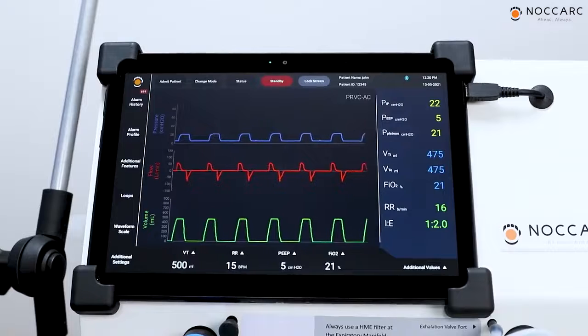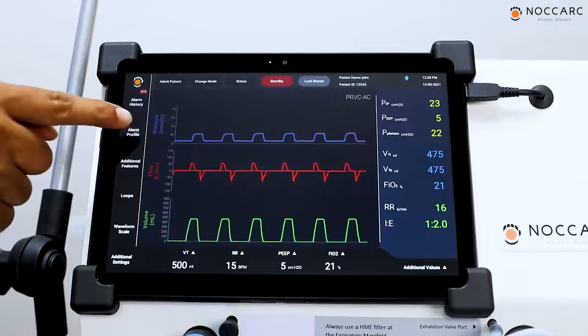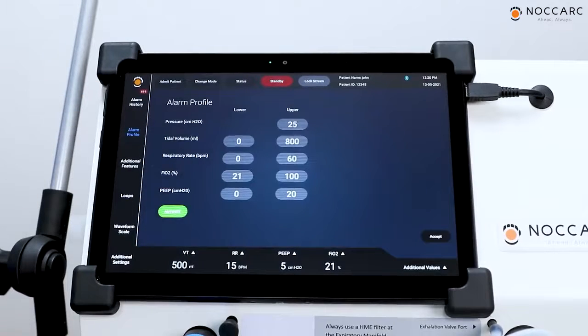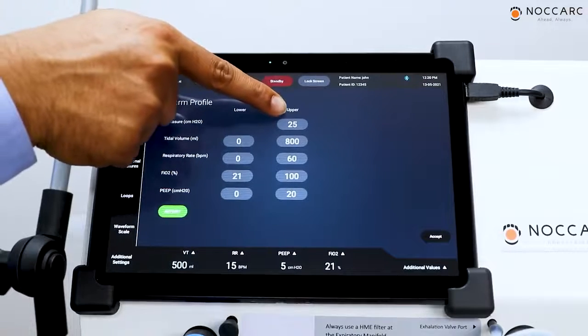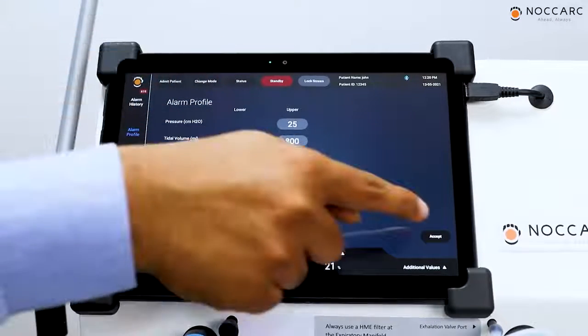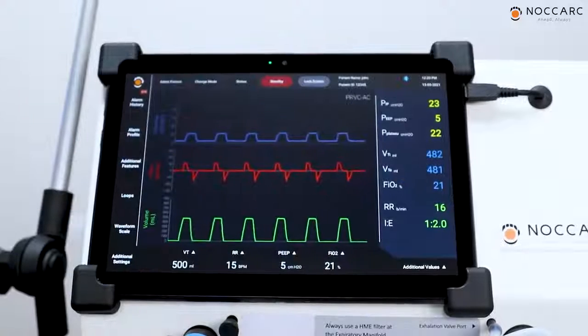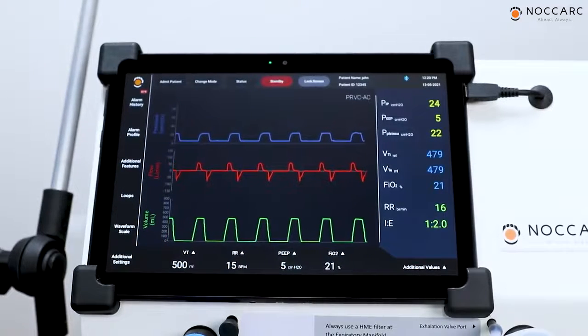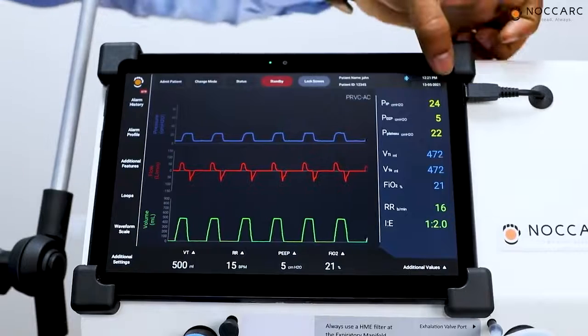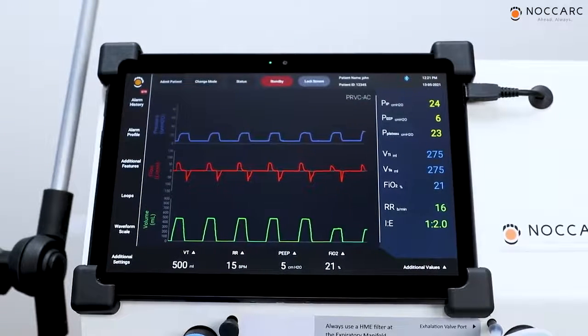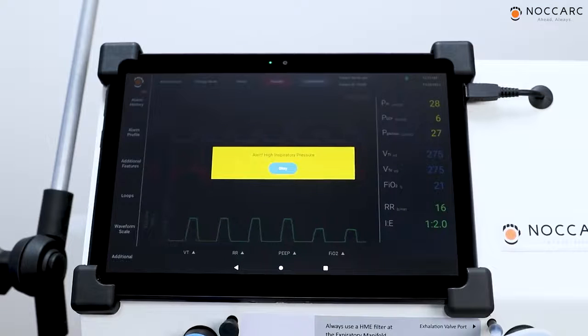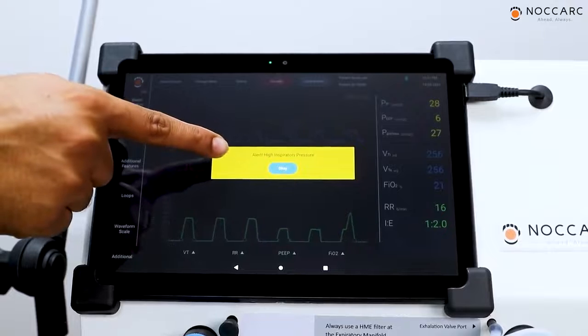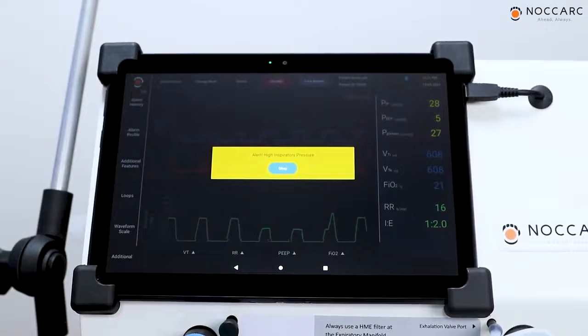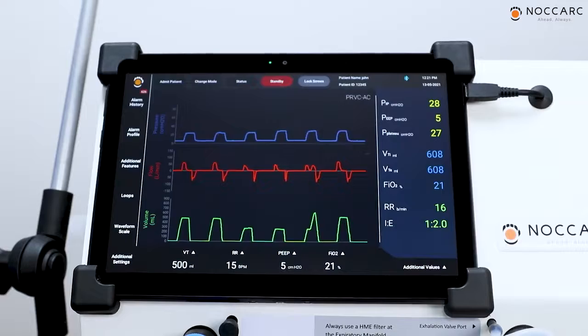To test high inspiratory pressure alarm, press on alarm profile. Here you can see upper limit for pressure is 25. Press on accept. If inspiratory pressure goes beyond 25, it will give the high inspiratory pressure alarm. Here you can see on screen high inspiratory pressure alarm is coming. That shows your inspiratory pressure is exceeding the limit.